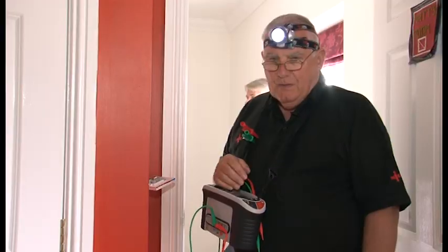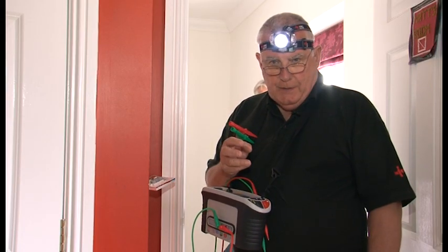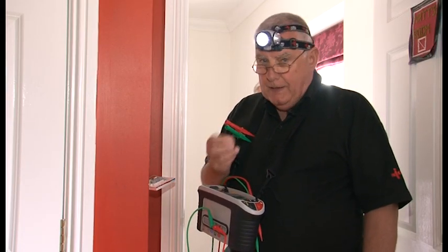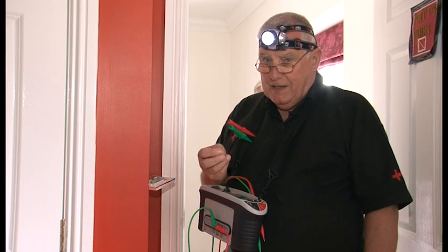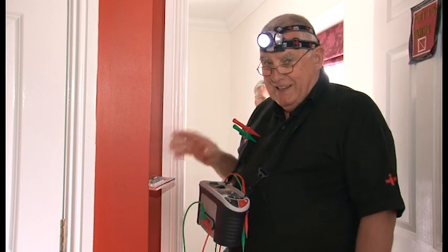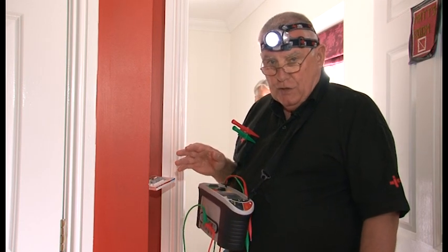So we've shown that the R1 plus R2 will also prove polarity for a lighting circuit without the need to remove lamps. Just a quick word about polarity. If there had not been an electrical installation certificate for this installation, I would have undertaken this test at every switch position to verify the polarity. Later on in the video, we'll see how to determine the earth fault loop impedance of these circuits and how to check that this is acceptable.